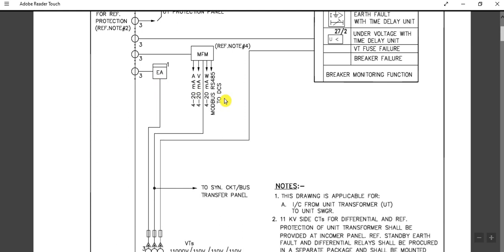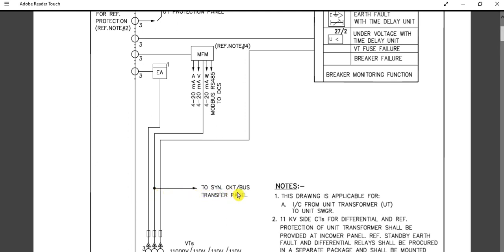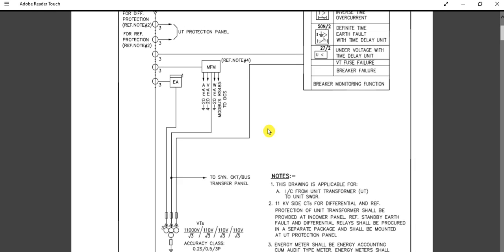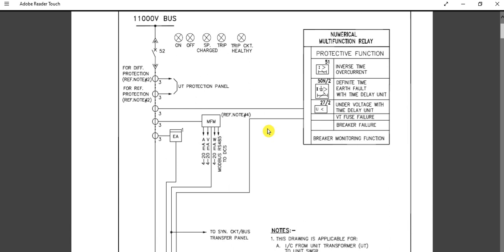From this VT there is also a tapping to the synchronizing circuit bus transfer panel. If there is an ABT (automatic bus transfer) panel, this VT voltage signal is required and will come from here. This is the typical 11kV or 6.6kV single line metering and protection diagram. Note that differential protection and REF protection are provided for medium voltage higher-rated feeders.